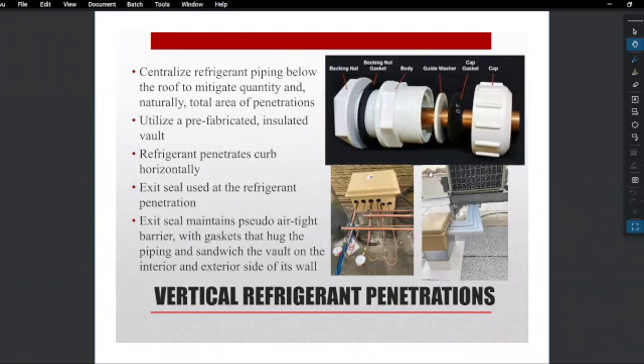With our penetrations for the refrigerant, what we typically do is, obviously, these penetrations are another source of air penetrating the building. So we have to make sure that we seal around the refrigerant pipe as it penetrates the roof, and we do this by using an insulated prefabricated vault. And with that vault, we cut out those holes for the refrigerant, and then we use what's shown in the upper right hand corner, what's called an exit seal. Basically, there's a seal on the inside and the exterior of the vault, and that gets screwed down and sandwiches between the interior and exterior wall of the vault, and also hugs the pipe. So it maintains that air seal.